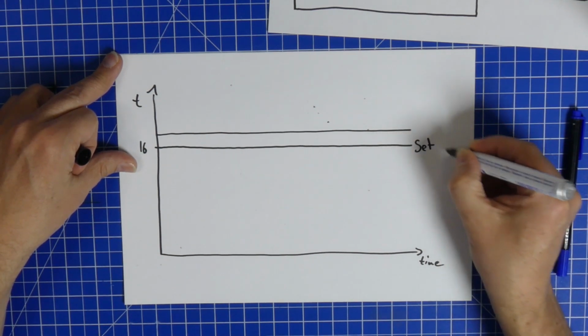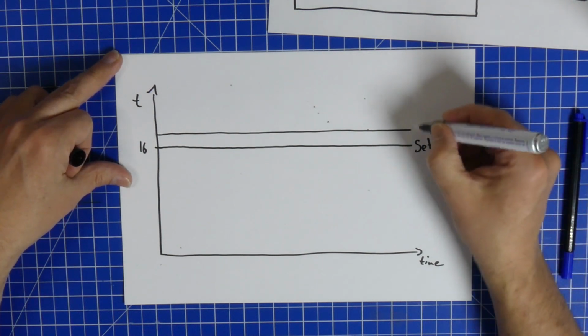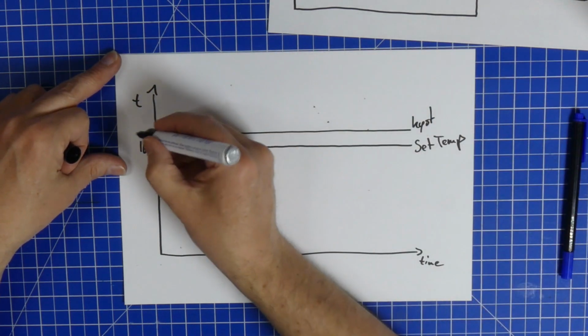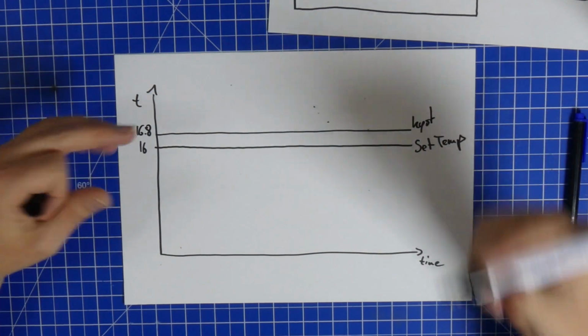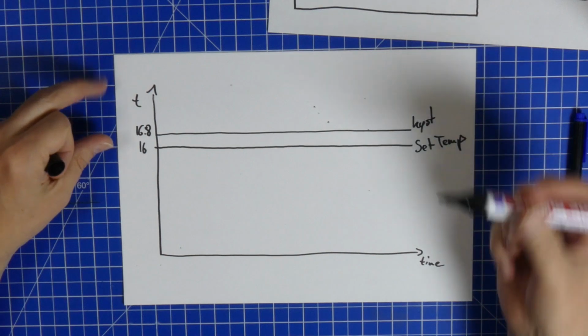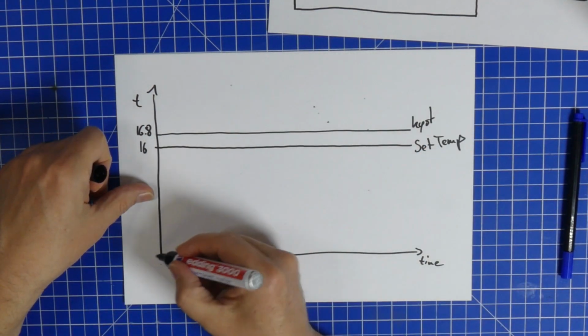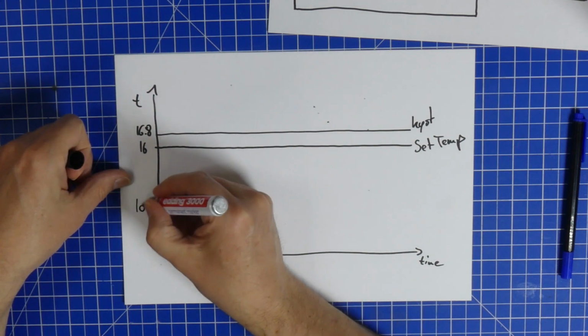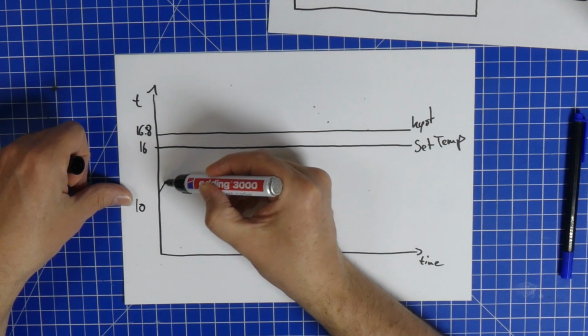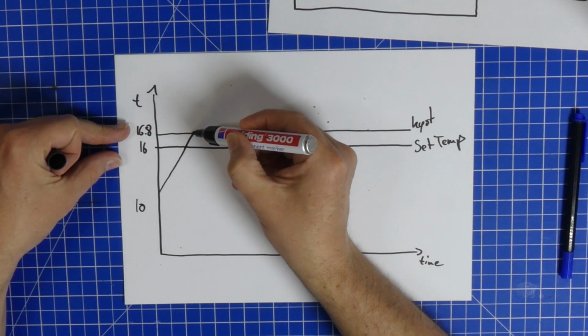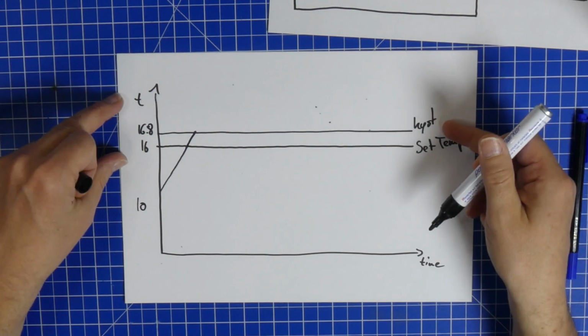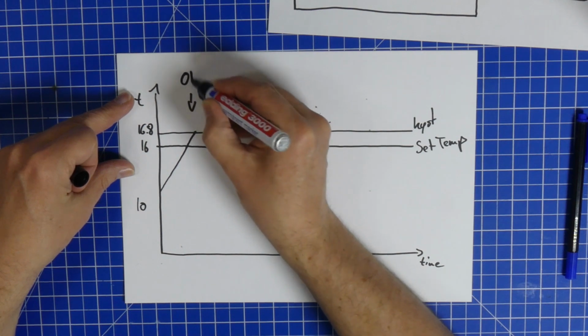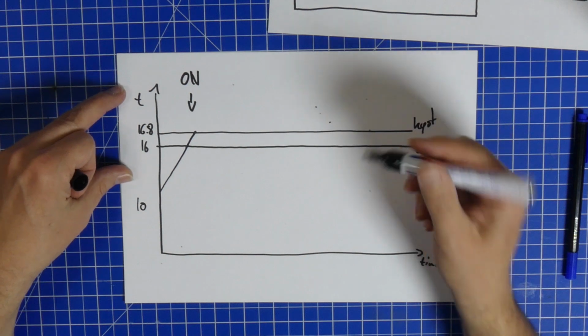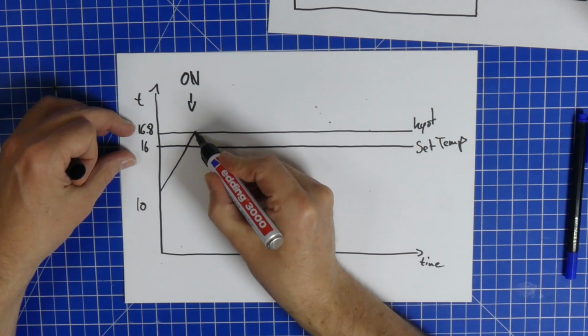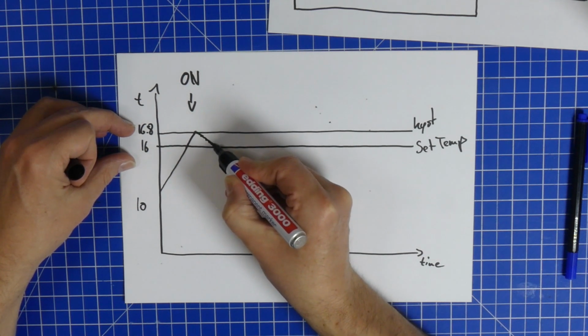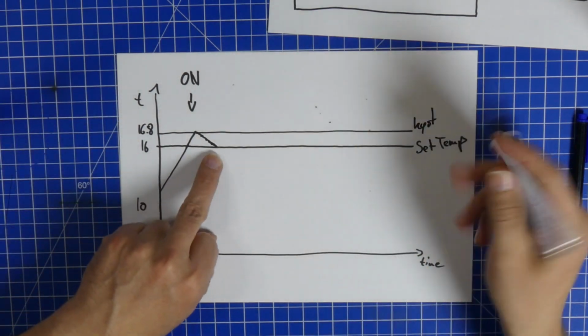This here is our set temp, which is 16, and our hysteresis is 16.8. Now, fine. Usually, now we start out and we've got a temperature, I don't know, we're starting out at 10 degrees. Over time, our temperature is going to rise. It is going to go past the 16, and it's going to hit the 16.8, which is the set temperature plus the hysteresis. At that point, our cooling system turns on, and it turns on full power, and it's going to start dragging this temperature down, and that is going to go pretty quickly up to the point where it hits the set temperature.